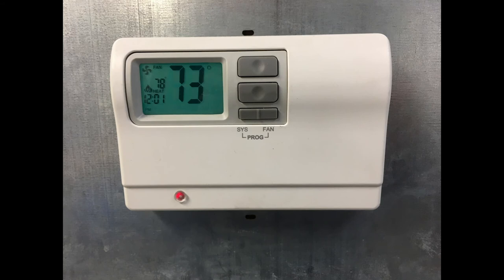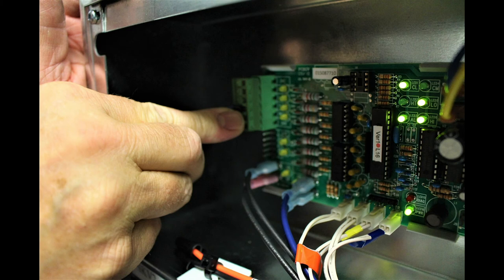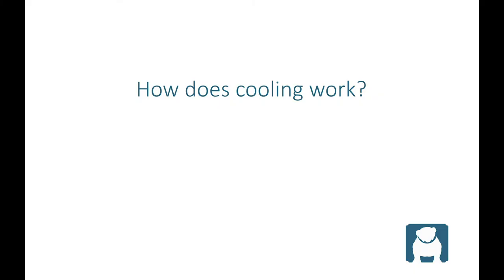How does the heat pump operate in standard heating? Firstly, a heating call has to be established by the thermostat. The WLED will light on the circuit board. The HT LED will light and so will the low fan LED. The heat actuator will open and low fan heating speed will be established.